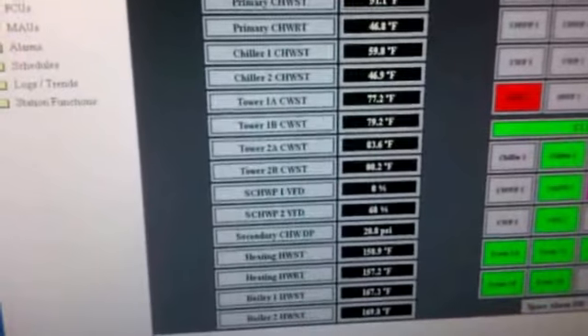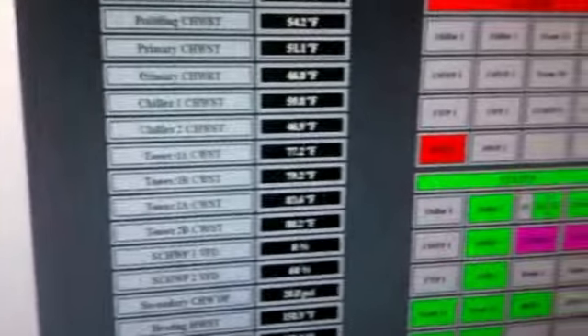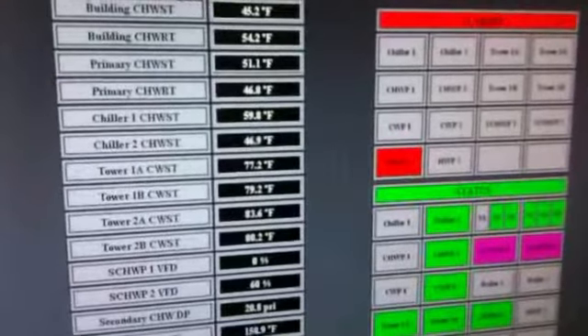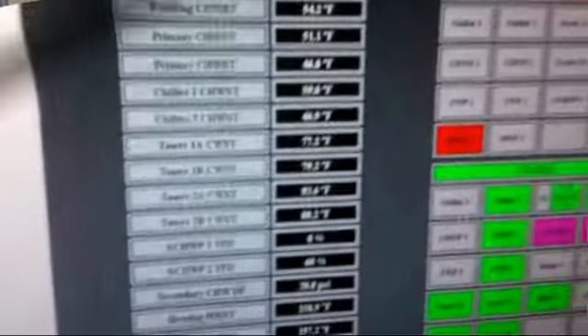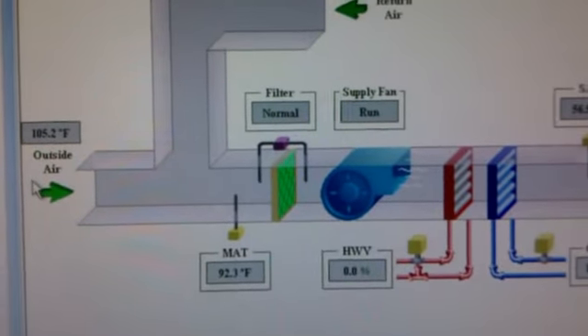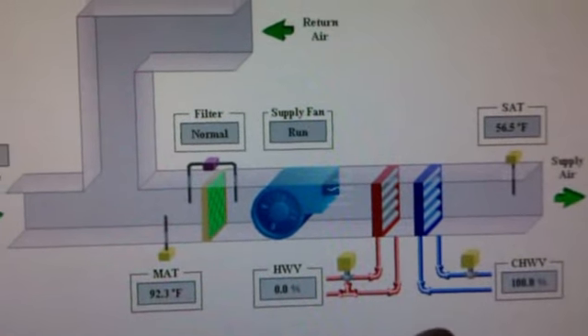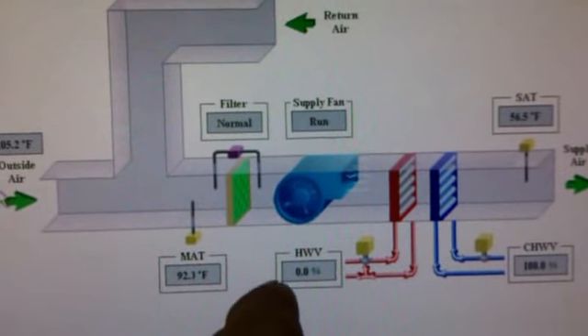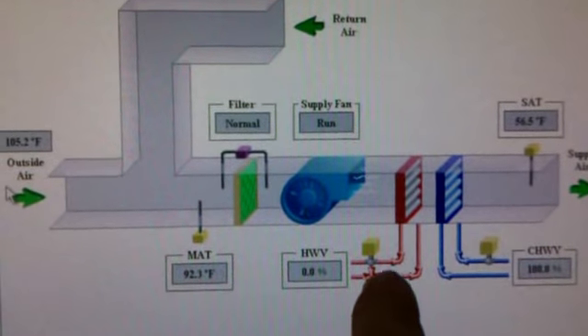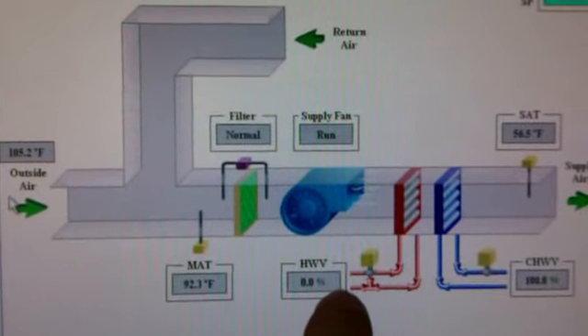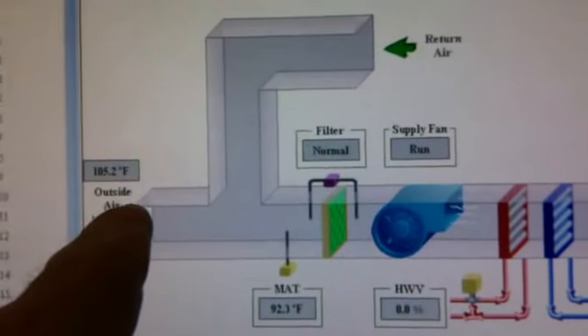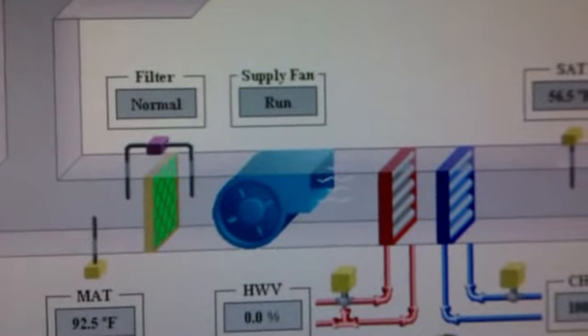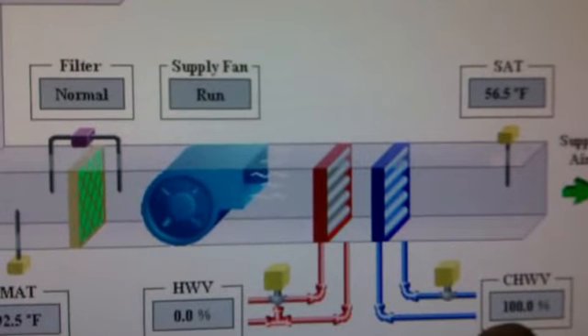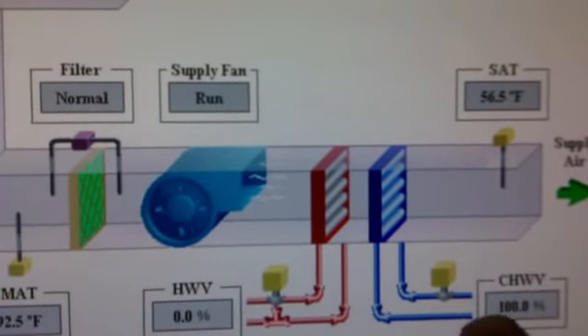And the other one is across the parking lot from me. And here's how the modulating water valves work. This is a 4-pipe system. This is hot water loop from the boilers, which of course don't need heat when it's 105 degrees outside. Chilled water valves at 100%. These are modulating valves, so it's anywhere in between.